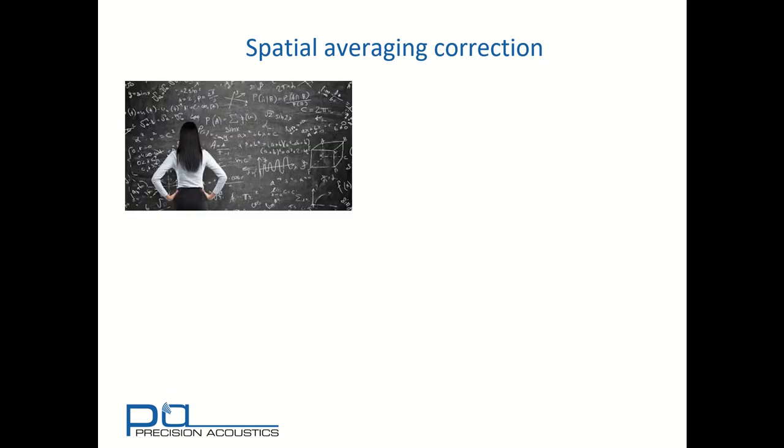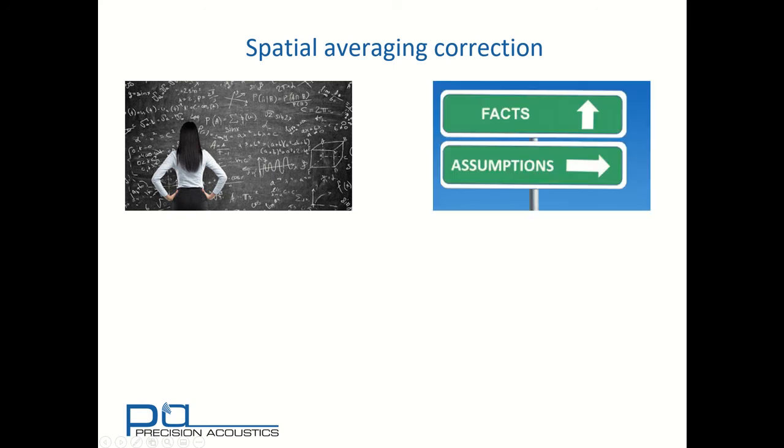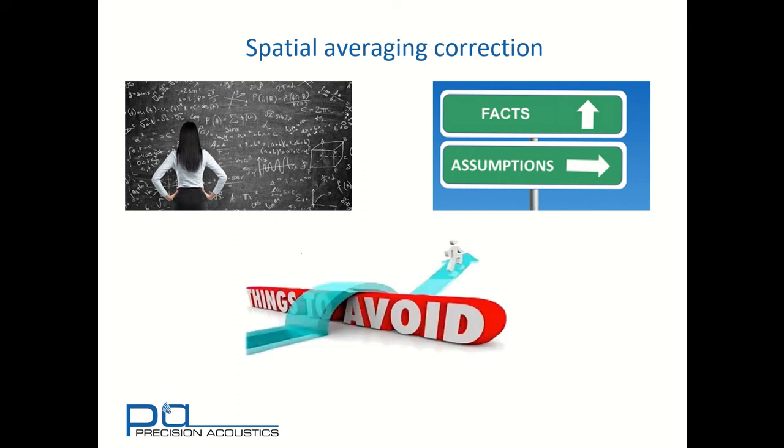There are some mathematical spatial averaging corrections but it's important to realise that they're mathematically complex and they also rely upon assumptions about the geometry of both source transducer and receiving hydrophone. And sometimes the experimental facts and these assumptions are inconsistent. Therefore as a general policy spatial averaging is something that should best be avoided. Where possible don't try to correct for it but make a measurement with the smallest hydrophone you can to minimise spatial averaging artefacts.